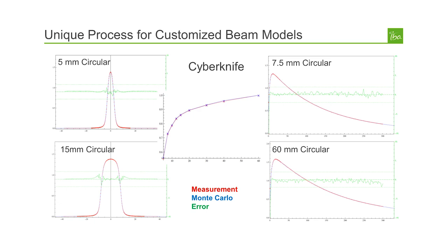To achieve a high level of accuracy in the clinic, it is necessary to customize the beam models of the Monte Carlo code to a particular linear accelerator. We have created a unique process for beam model customization that allows us to achieve very high accuracy in practice. Shown here are water phantom dose measurements for a CyberKnife beam, including depth dose curves for a 7.5 mm and a 60 mm circular field. The red curve is the measurement, the blue curve is the Monte Carlo simulation, and the green curve is the error. We achieve an accuracy of less than 0.5% in the depth dose curves even for these very small field sizes.